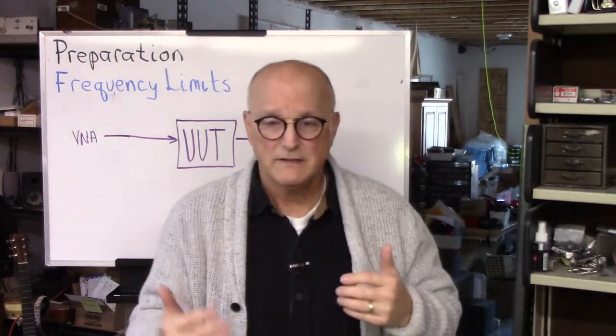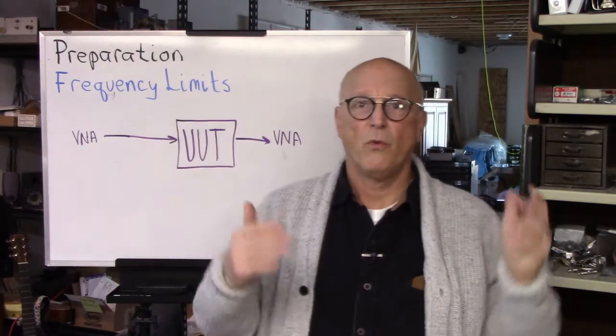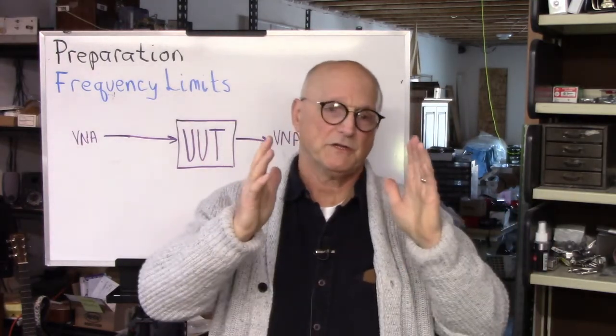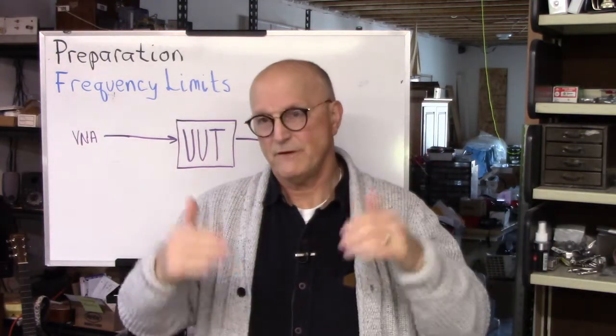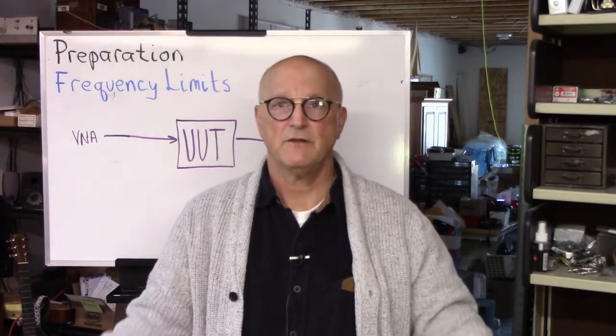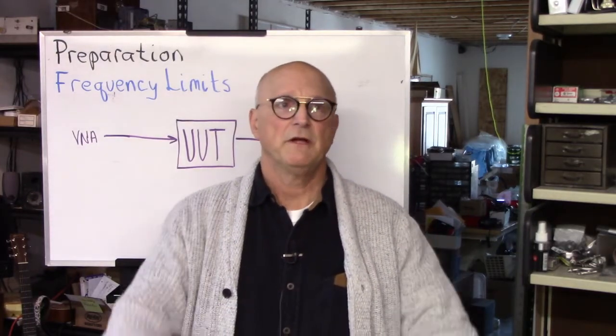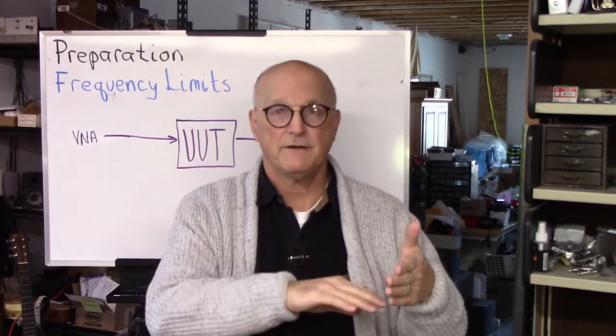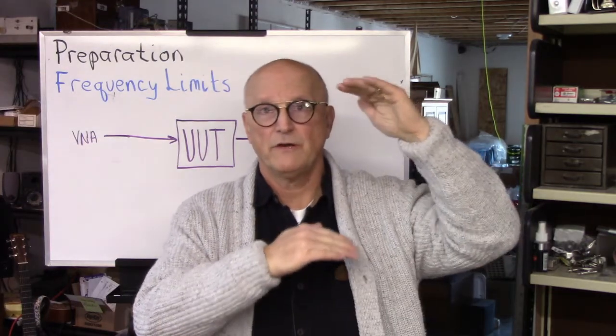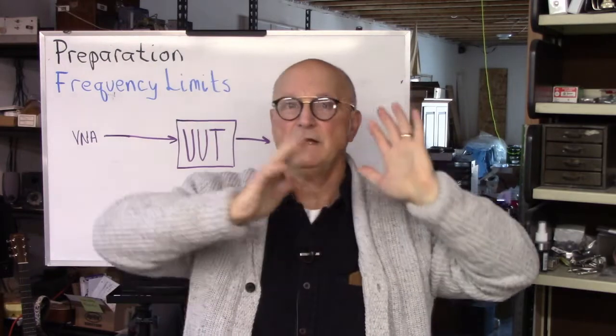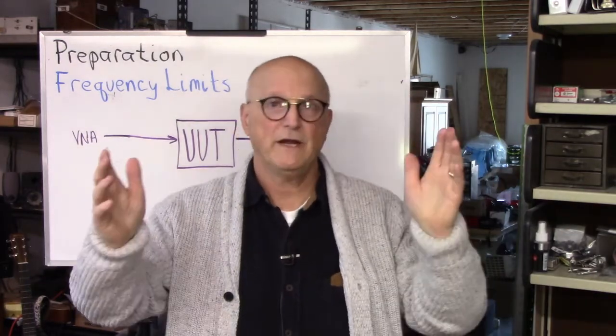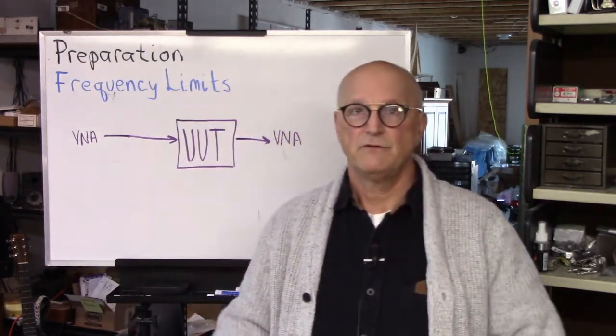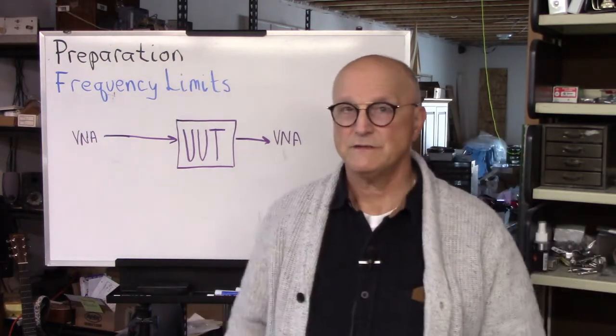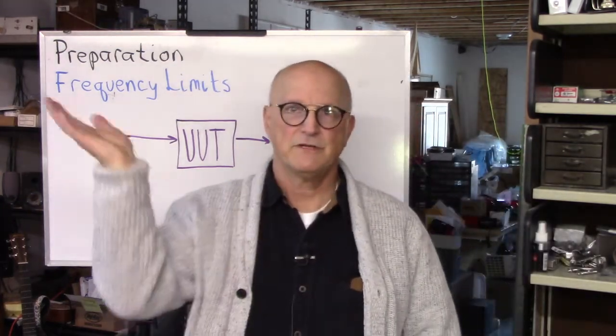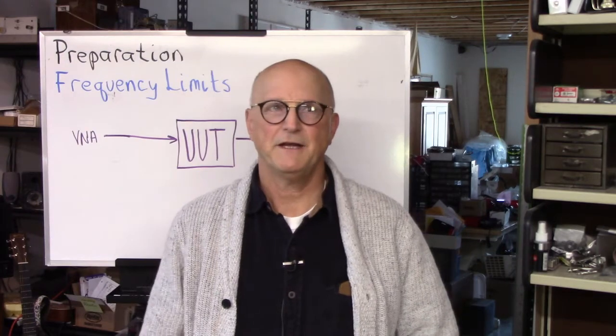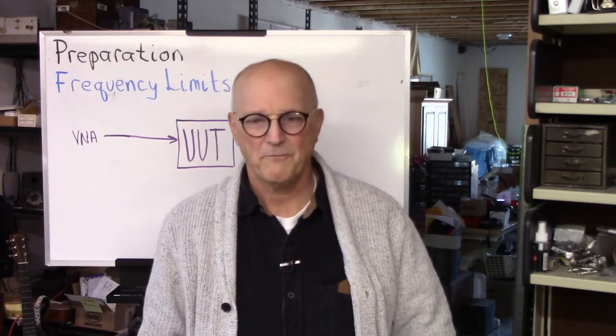In the Mini VNA Tiny, they have Mode 1 calibration, where, if you carefully follow the instructions in the software manual, there is a file that you can edit, but it's still going to require you to calibrate the entire frequency range of the device. If you don't cover the entire frequency range of the device, it throws the file away that you just edited and sticks its own in there.